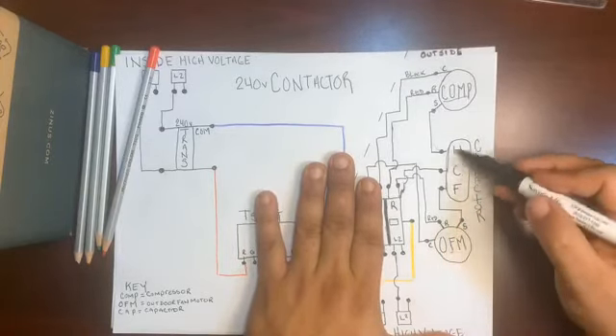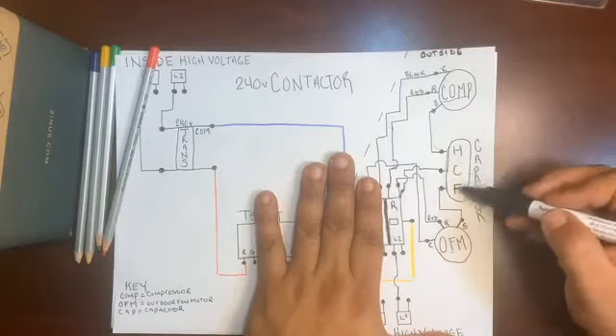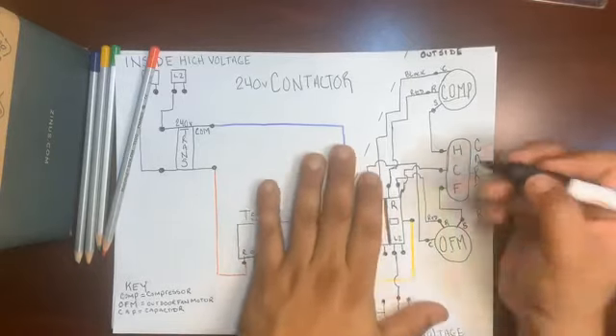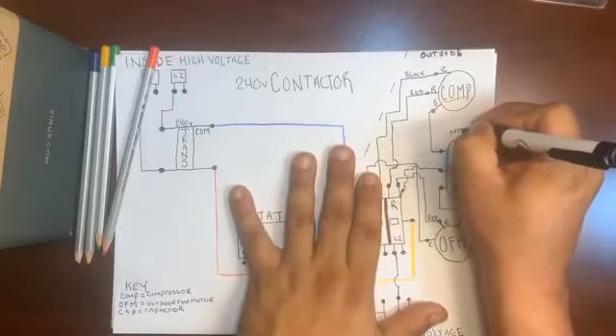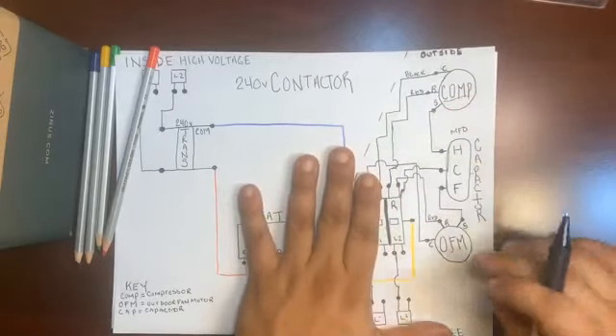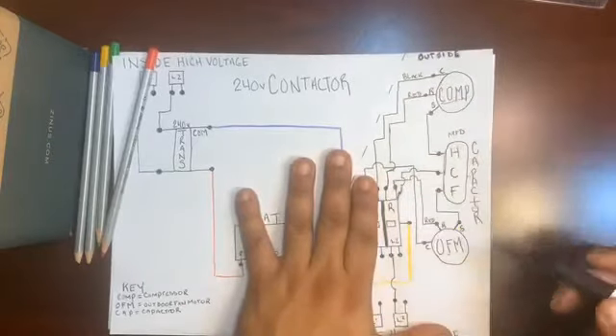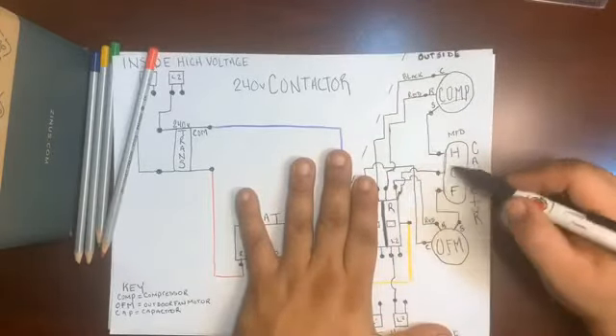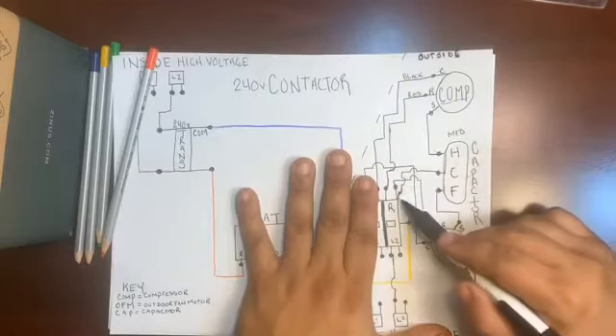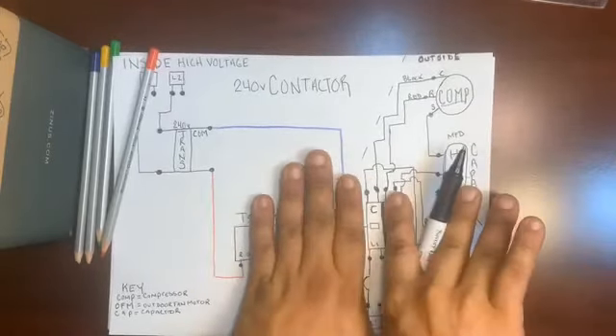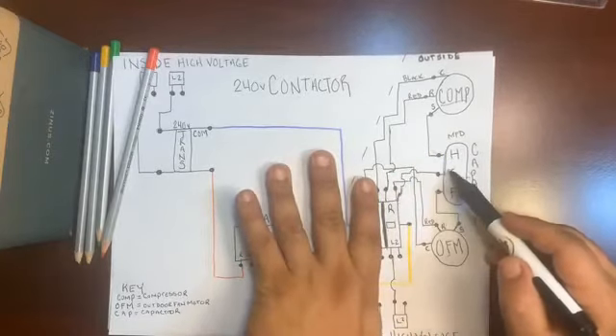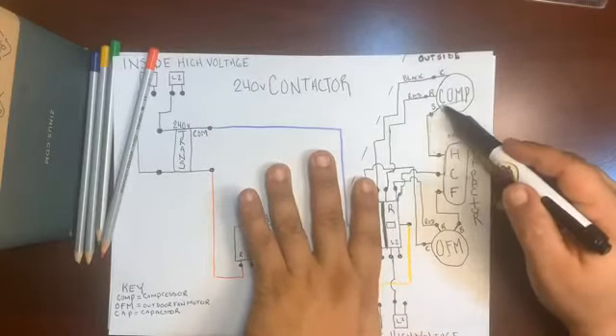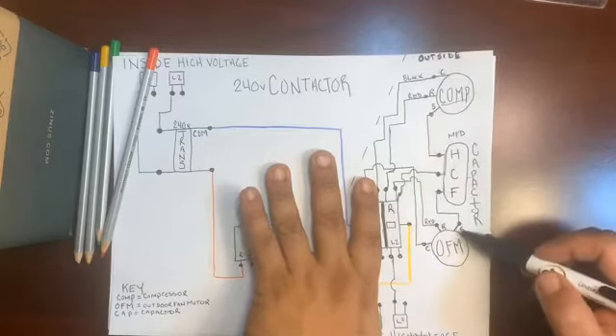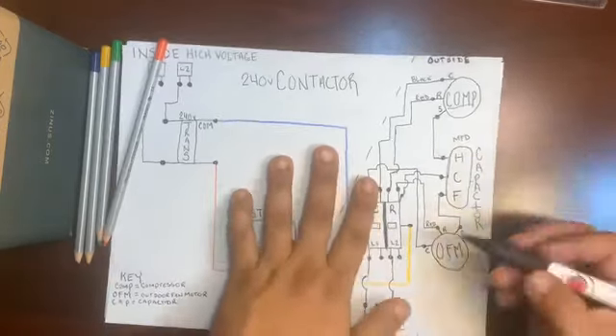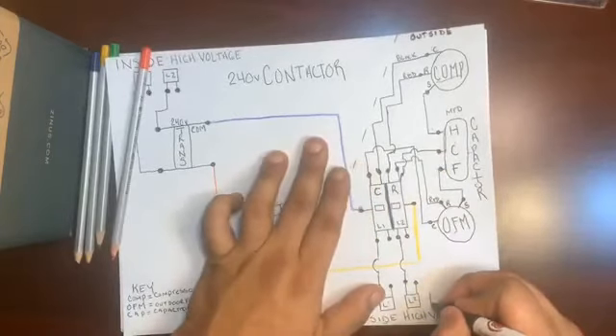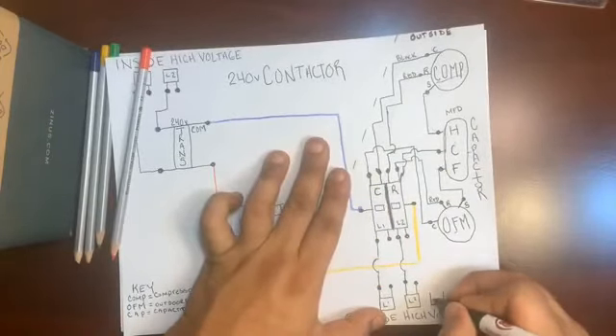So what this capacitor is doing is maintaining a charge rated in microfarads. It's MFD, microfarad rated. We're going to get more into capacitors, but we're just sticking to the diagram right now. This is what a capacitor does: it holds a charge because it's being fed from the run side, not the common side. It's being fed from the run side, creating a charge, and then we're feeding a leg into the start leg of the compressor and the start leg of the outdoor fan motor. And this is what a capacitor does. It eliminates the need for us to have L3 down here.